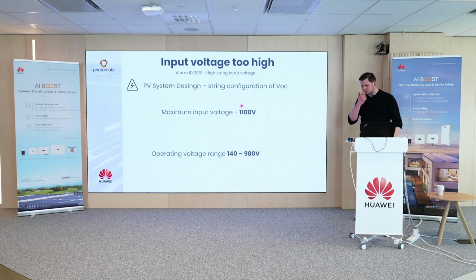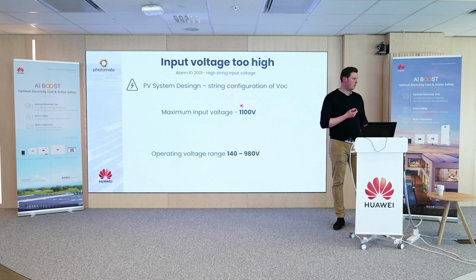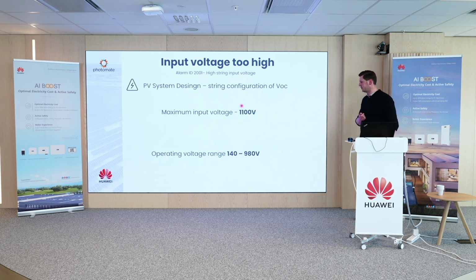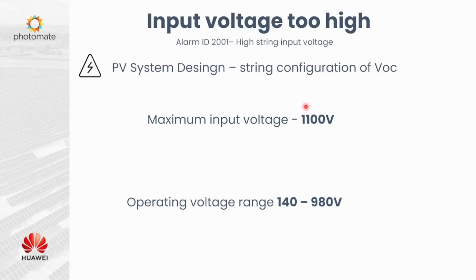Some information may be more related to designing PV systems, not installing them, but there are two parameters in the datasheets. If you look carefully, you have 1100 volts maximum input voltage and operating voltage range up to 980. This is the value you should relate to, not the other one. If the limit is crossed, I mean the 980 volts, your inverter will shut down because of string over voltage.